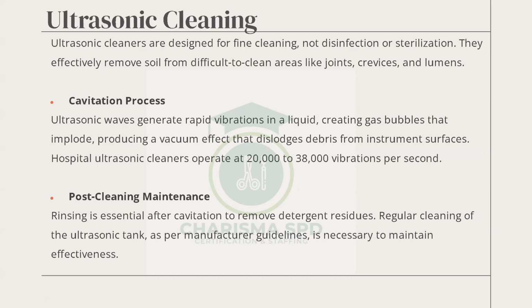All right? Hospital ultrasonic cleaners operate at 20,000 to 38,000 vibrations per second. And it is through these vibrations that the bubbles implode and produce a vacuum that dislodges the debris from the instrument surfaces. All you need to know is the cavitation process. It must be second nature to you. Even when you're sleeping and someone asks you, what is it? Oh, it's associated with the ultrasonic cleaning, and that's how it cleans.